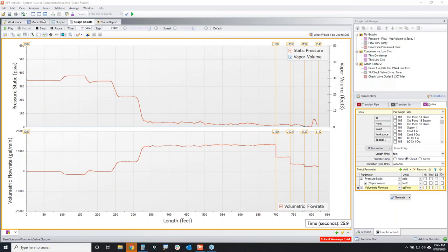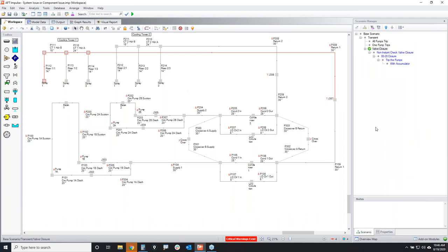So that's what's going to be happening in the downstream part of my system. And, you know, as long as you understand what's going on, when you see those really high pressures, those are going to be conservative upper limits, because that's assuming liquid densities. If you were having pressure surges with air filling the pipes, it probably wouldn't be as high due to the compressibility and the low densities of the gas that would be entering that part of the system.